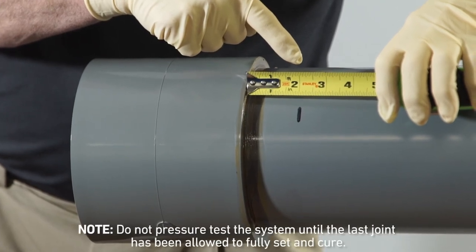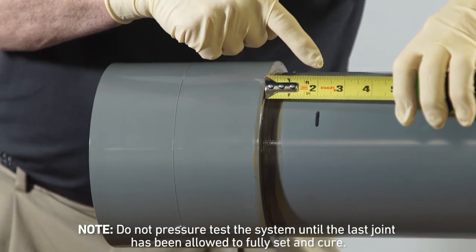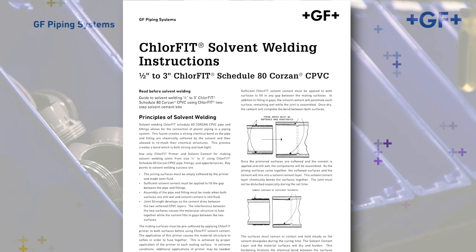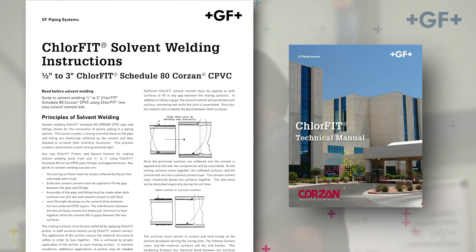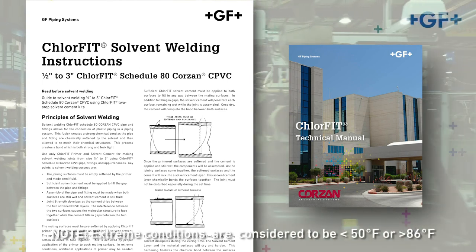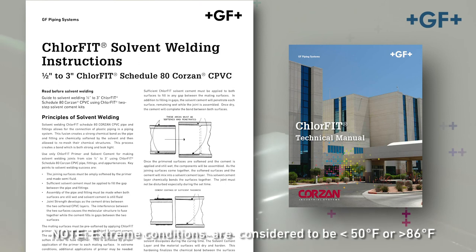Best practice includes labeling each joint with the installer's initials and date the joint was made. A table of set and cure times can be found in the installation instructions included, or the ChlorFit Technical Manual. For comprehensive instructions for solvent welding in extreme conditions, please refer to the installation instructions included in the solvent welding kit.